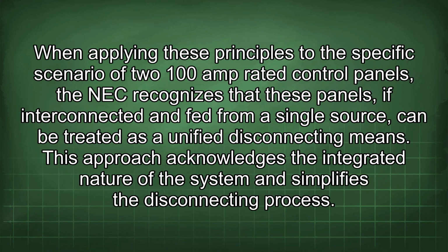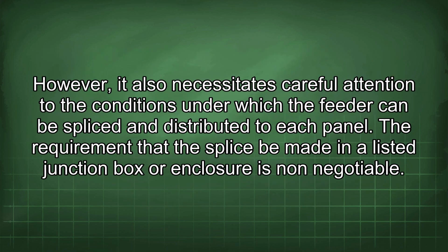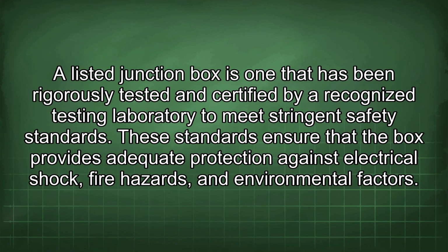When applying these principles to the specific scenario of two 100-amp rated control panels, the NEC recognizes that these panels, if interconnected and fed from a single source, can be treated as a unified disconnecting means. This approach acknowledges the integrated nature of the system and simplifies the disconnecting process. However, it also necessitates careful attention to the conditions under which the feeder can be spliced and distributed to each panel. The requirement that the splice be made in a listed junction box or enclosure is non-negotiable. A listed junction box is one that has been rigorously tested and certified by a recognized testing laboratory to meet stringent safety standards.